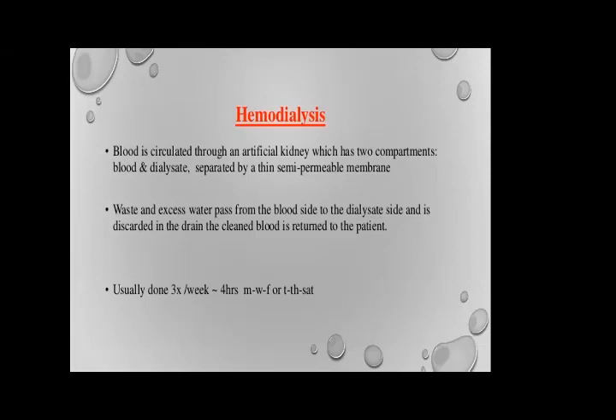Now we come to the more sophisticated area, which is hemodialysis. In this technique, we directly use our blood, which is passed through an artificial kidney that has two compartments, blood and dialysate, separated by a thin semi-permeable membrane, the same as the peritoneal membrane. From one side blood is put into the filter, and after filtration the waste is removed. I'll show you how the dialysis machine works. Waste and excess water pass from the blood side to the dialysis side and are discarded in the drain. The clean blood returns to the patient.